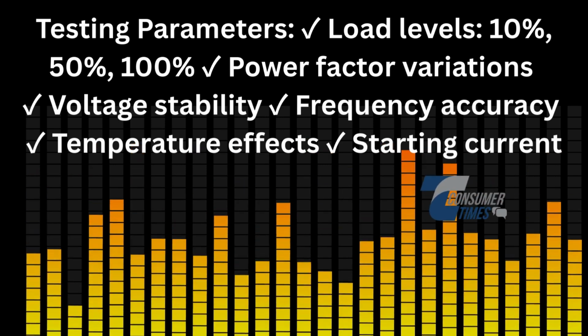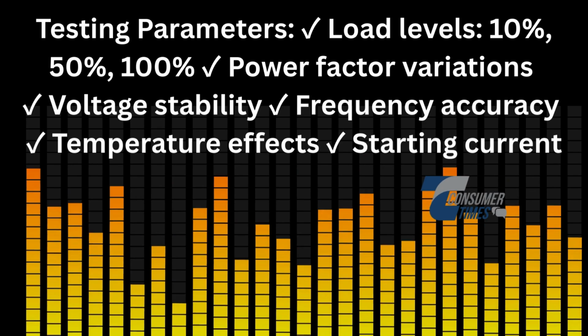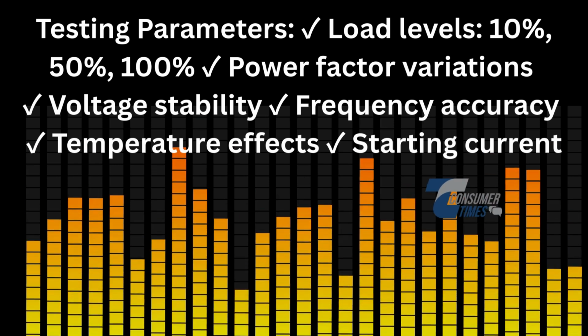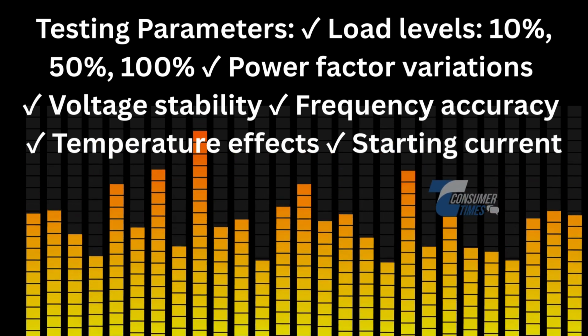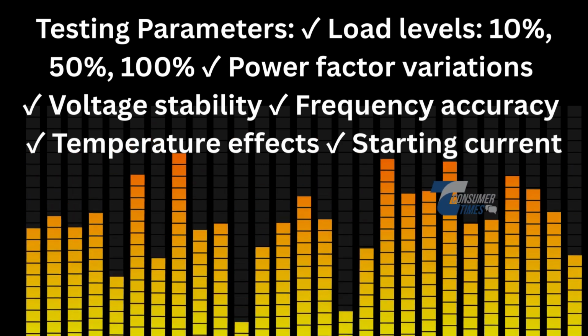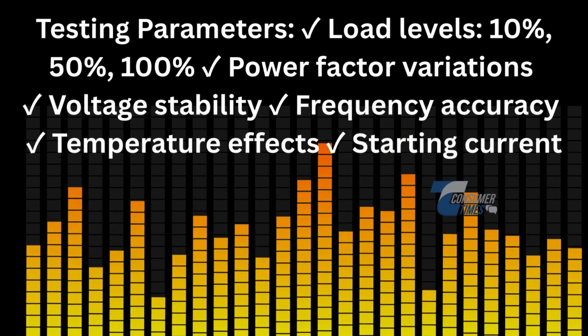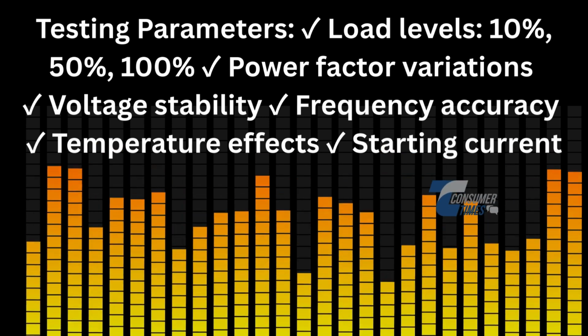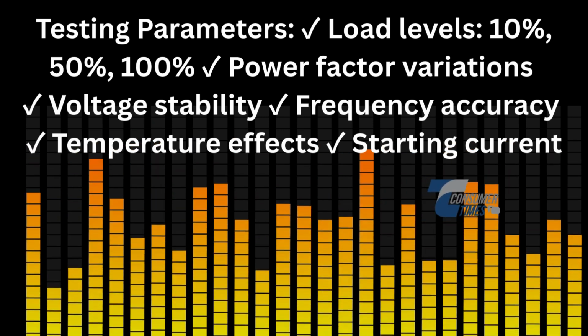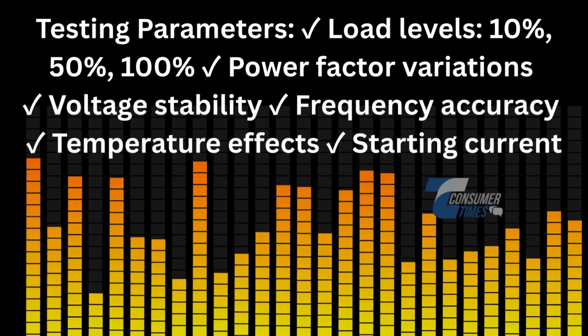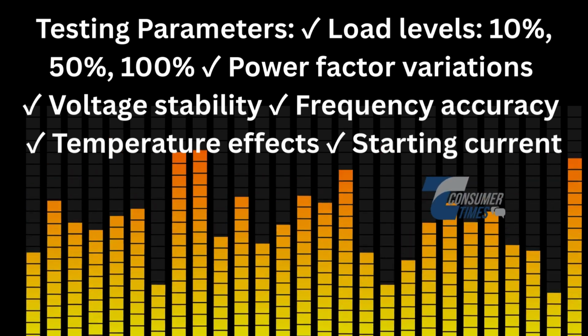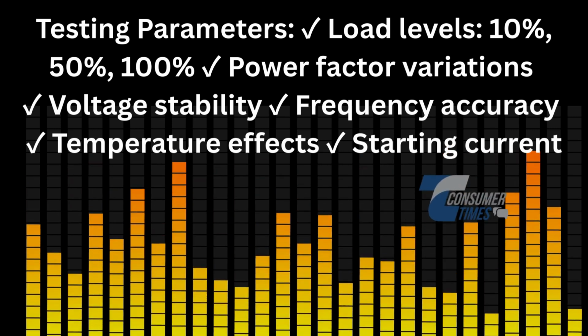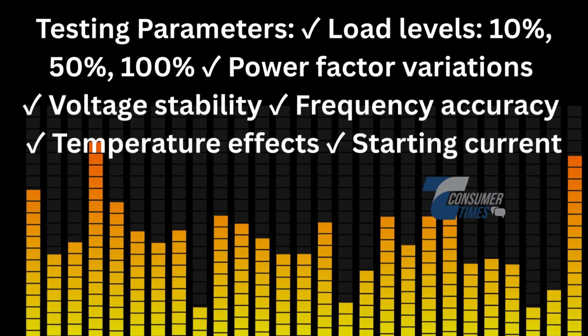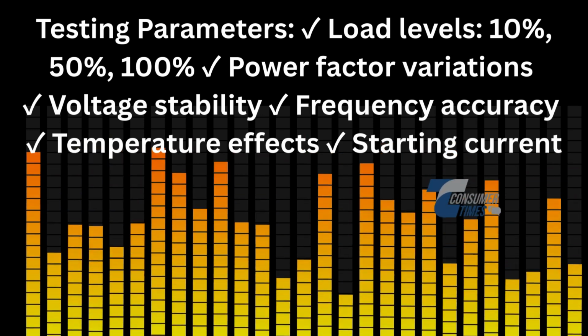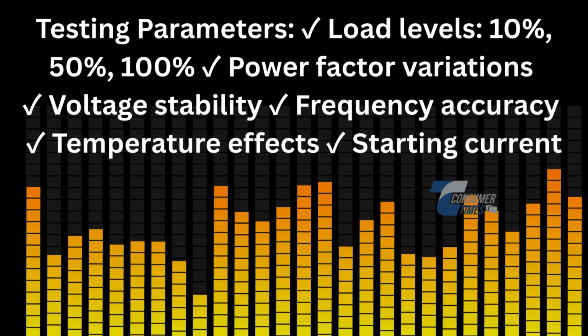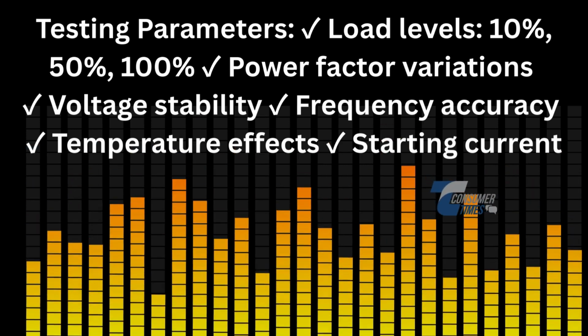Before we discuss testing, let's understand the types of meters currently in use. Traditional electromechanical meters, often called analog meters, use rotating discs and are becoming obsolete but still exist in many areas. These meters measure energy through electromagnetic induction. Then we have electronic or static meters, which use digital technology and have no moving parts. These are more accurate and can measure multiple parameters. Finally, smart meters represent the latest generation. They're electronic meters with communication capabilities that can send real-time data to the utility company and even allow remote disconnection and reconnection. Each type requires different testing methodologies, but the fundamental principle remains the same: ensuring measurement accuracy.